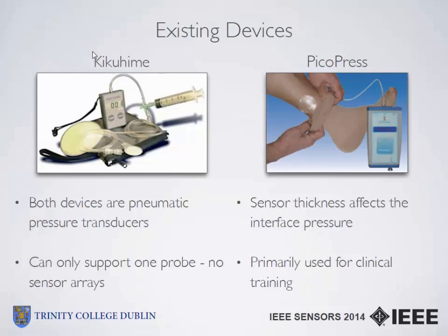Existing devices used mainly for clinical training include the Kikuhime and the Picopress. These devices are pneumatic pressure transducers and they only support one probe at a time, so you can't get an array of sensors — it's just for evaluation at one point only. The Kikuhime requires a lot of calibration before use with sensor accuracy of 2–3 mmHg. The Picopress is much easier to use, requires no prior calibration, and has sensor accuracy of 0.2 mmHg. But these are mainly lab-based, not portable, and can't measure multiple locations over a period of time.